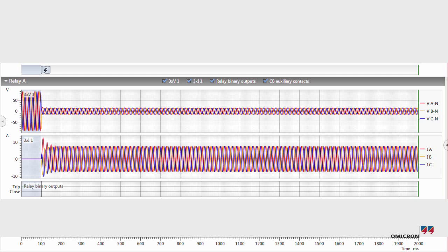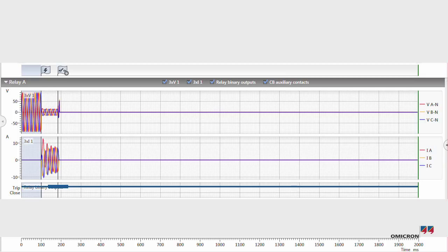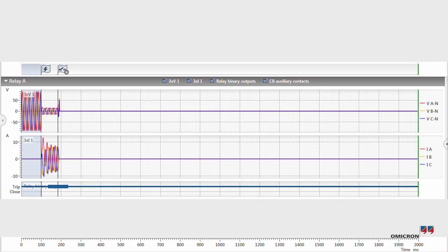At first, the test set injected a persistent fault. The relay reacted with a trip command. RelaySimtest remembers this relay reaction and incorporates it into the next iteration, simulating the circuit breaker opening.